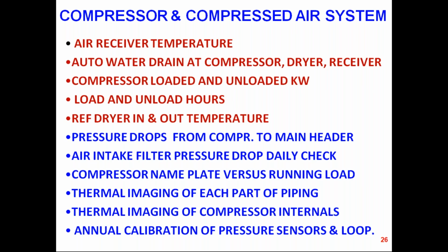Likewise, the automatic water drain at the compressor, the dryer and the receiver has to function, because the compressed air line cannot afford to have even water droplets, micro water droplets should not be there in the compressed air line. You will find when you open the receivers, so many buckets of water can be collected. If water is more in the compressed air line, then the pneumatic health of the process gets affected and a lot of failures in the machines happen.